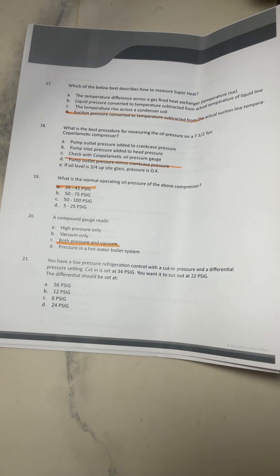21, I think we'll end it here. You have a low pressure refrigeration control with a cut-in pressure and a differential pressure setting. Cut-in is set at 34 PSIG. You want to cut it out at 22 PSIG. The differential should be set at what? A, 56 PSIG, B, 12 PSIG, C, 6 PSIG, or D, 24 PSIG. The answer to 21 is B. That's 12.